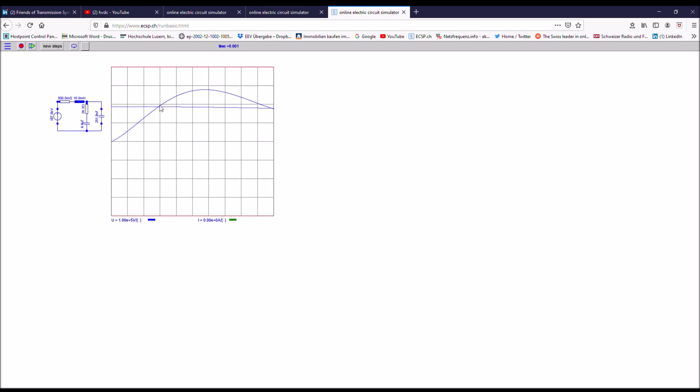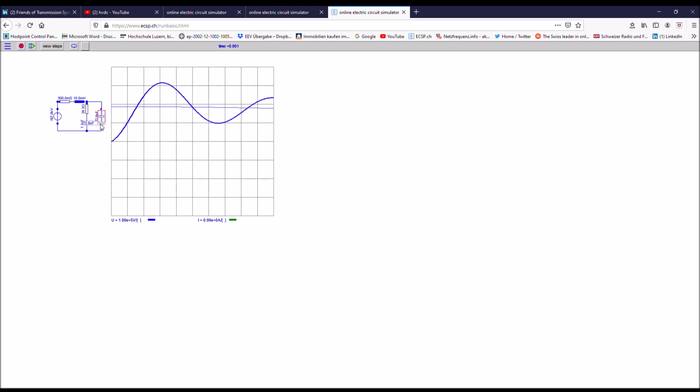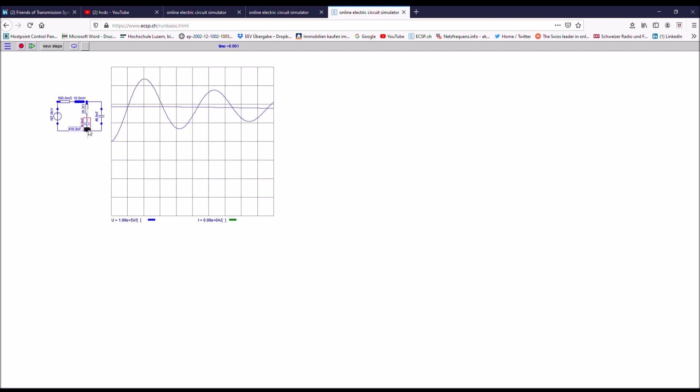Therefore, I have to increase the slope of this TRV. This means I need to increase the frequency. I reduce the delay time. I further increase the frequency. Now you see that I have to improve the damping as well, slightly. Now I am more or less where I should be.